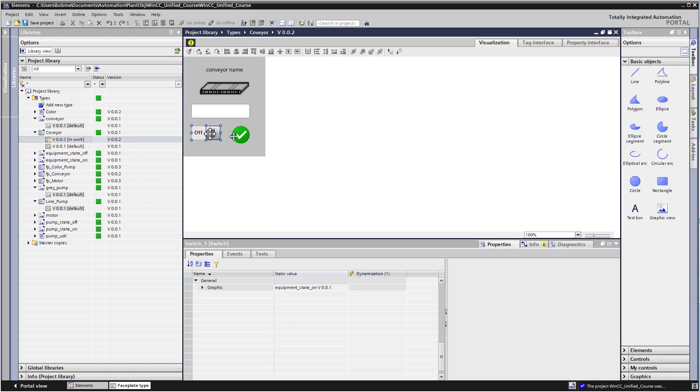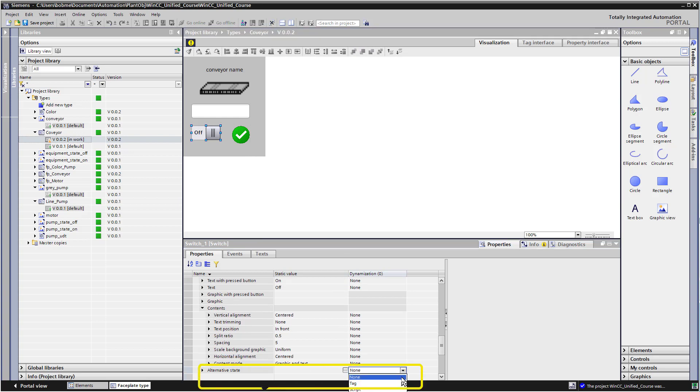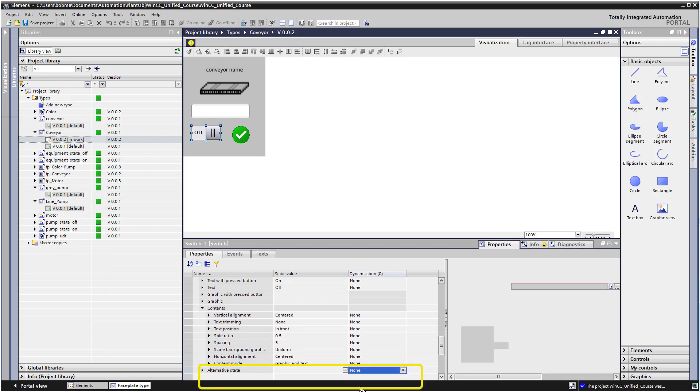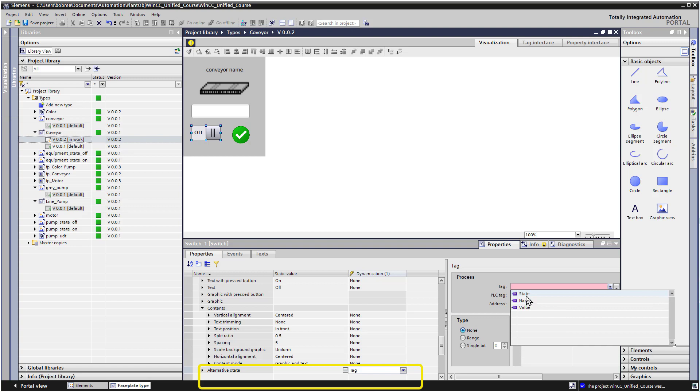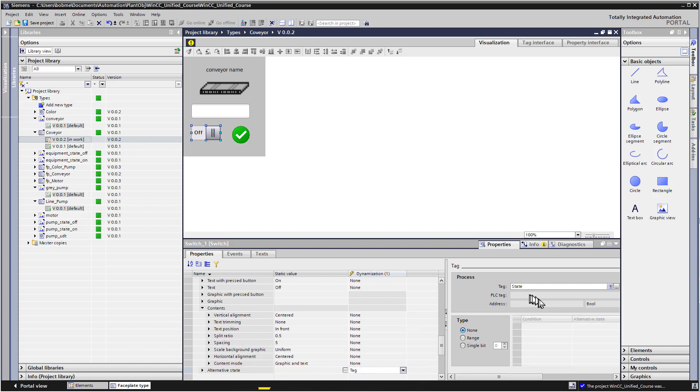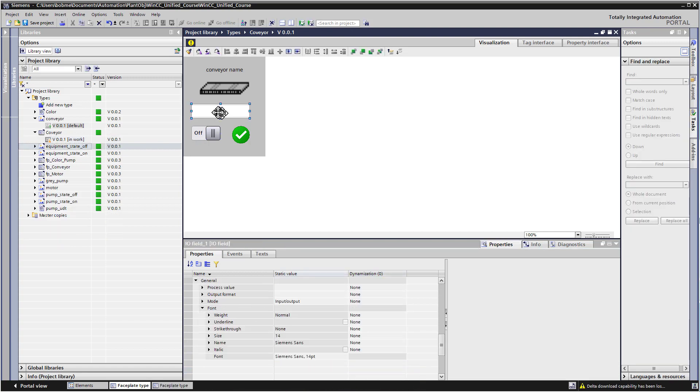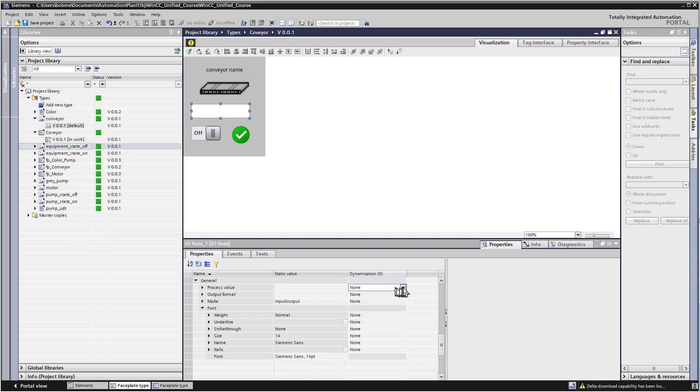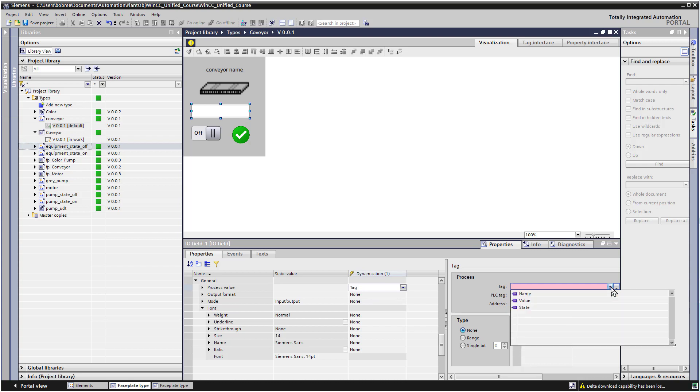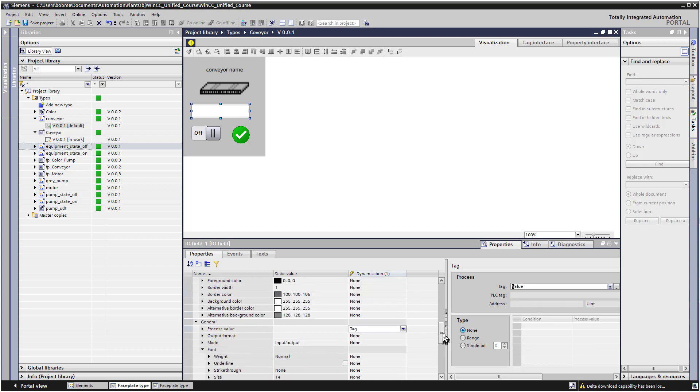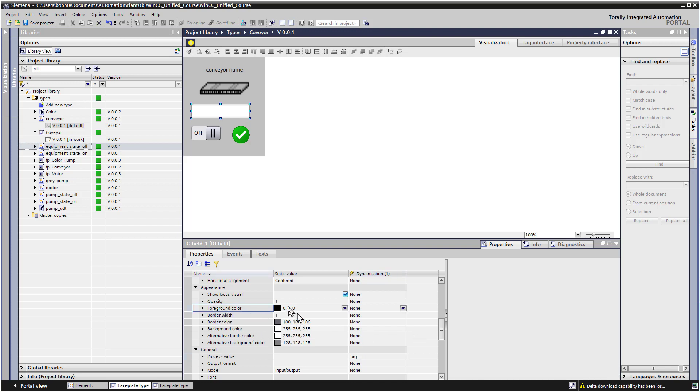And then on our switch here, on the alternative state, we need to do a tag interface and also set this to our state tag. And then for our IO field, the process value is going to have the tag dynamization. And we're just going to add value to that. And then I'm just going to go up and make sure our foreground color, which is our font, is black. Background color is white. So that should work for us.